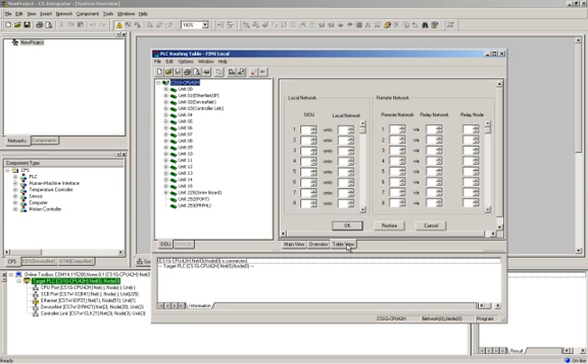A local routing table is the part that assigns network numbers to the network cards on the PLC backplane. The relay routing table describes the path to get to network numbers that are not physically present on the PLC for which the routing table is being created. For the purposes of this video, I will create only the local routing table, which is a typical configuration for simple networks.